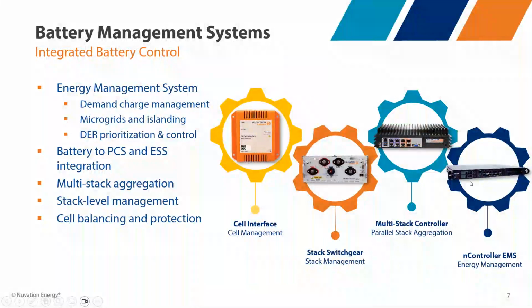Here's a quick overview of our primary products. We have the cell interface, which sits closest to the cells, measuring individual cell voltages and temperatures and doing balancing. That rolls up in a string to our stack switchgear. Stack switchgear is the level at which functional safety resides - this is our UL 1973 product. It has inside of that all the algorithms for state of charge, state of health, balancing, as well as the power equipment, contactors, fuses, and current shunt.